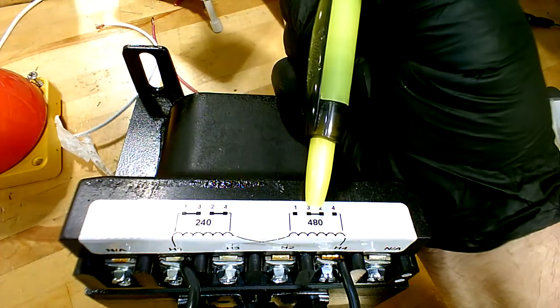You use two jumpers if it's going to be 240, and a single jumper in the middle if it's going to be 480. So for low voltage, in the range of 208 to 240, you do two jumpers. And if it's going to be high voltage, anywhere from 460 to 480, you put one single jumper in the middle. You see those lines? See that line in the center there? That's a jumper. What that does, when you put two in there, it puts that winding and that winding in parallel. If you put a single jumper in, it puts those two windings in series. I'll get into that more later.